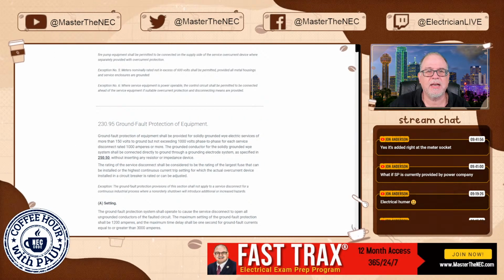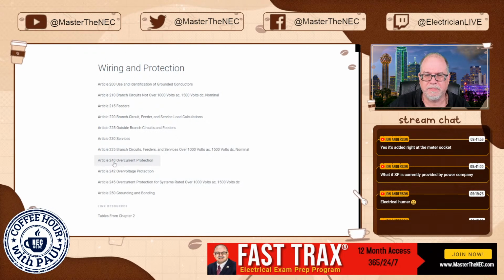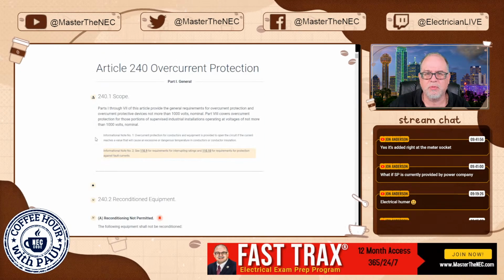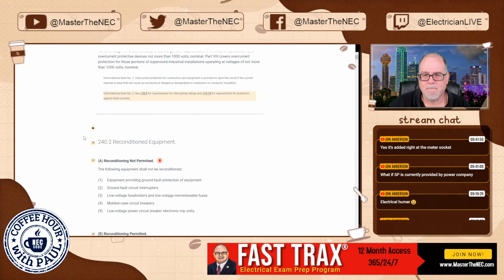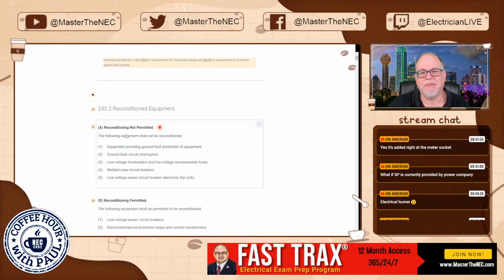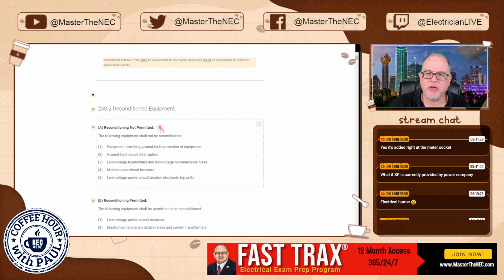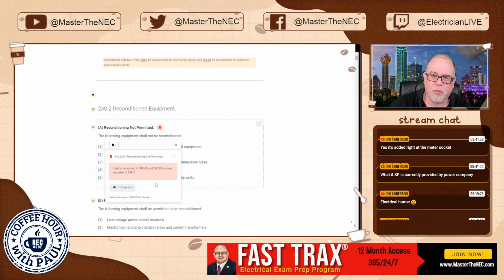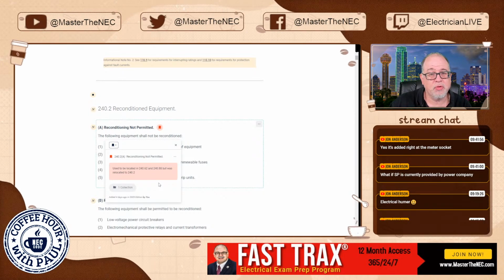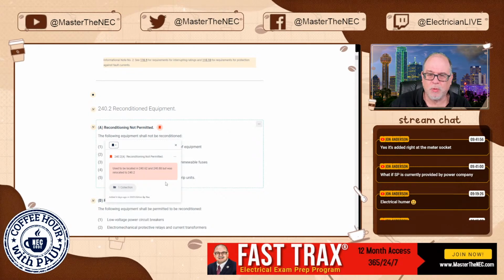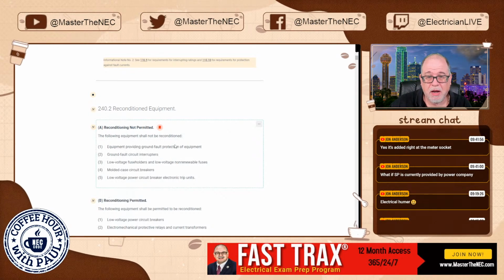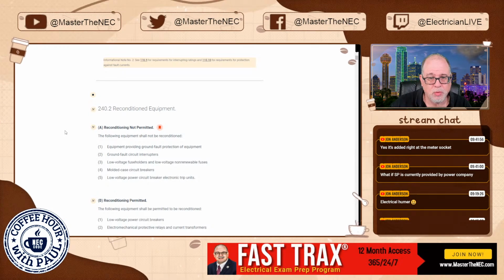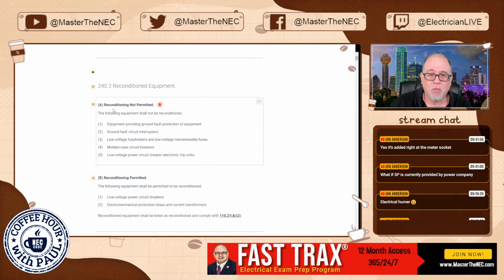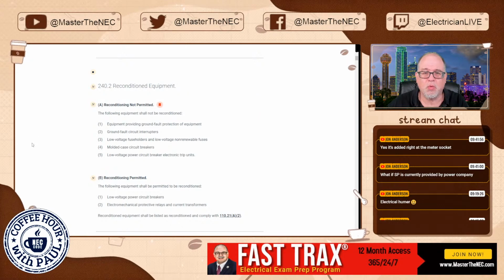Okay, all right. So the next one we'll go to while we're here is 240. All right. So 240, we have 240.2 reconditioned equipment. And I'll click here and it says used to be located. This used to be located in 240.62 and 240.88. When it comes to reconditioned equipment, guess what? It's just been moved. So now it is here in 240.2(A). Right? So reconditioning that is not permitted. So this tells you what is not permitted.